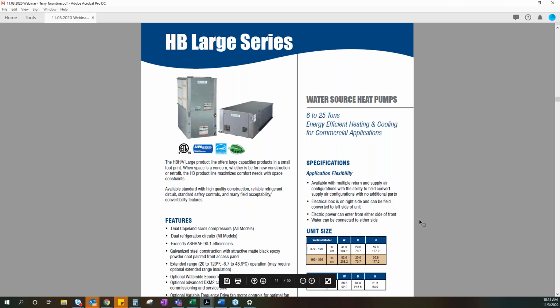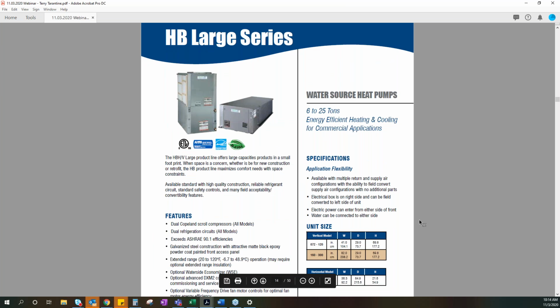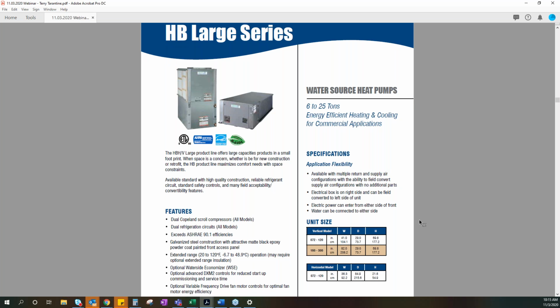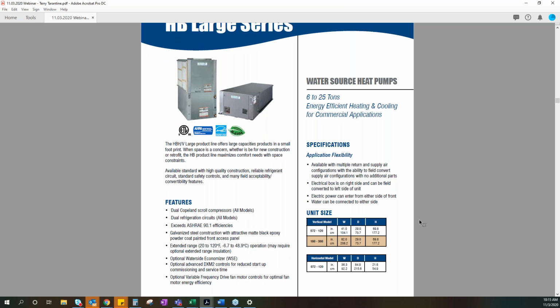Water source heat pumps. This list shows 6 to 25 tons. I chose this particular sheet because we are trying to maintain that 10 ton, but just be aware that these systems do go down to fractional tonnage as well. And we often see this in water source heat pumps. We'll have a multitude of smaller systems in an office building doing zoned heating and cooling for different spaces. In this one, we look at both vertical and horizontal models. The vertical goes from 6 to 25 tons. The horizontal goes from 6 to 10 tons.